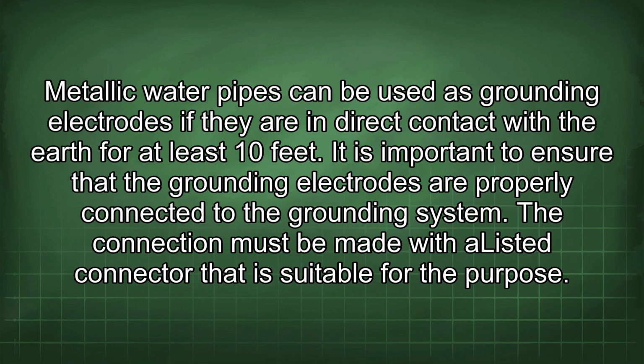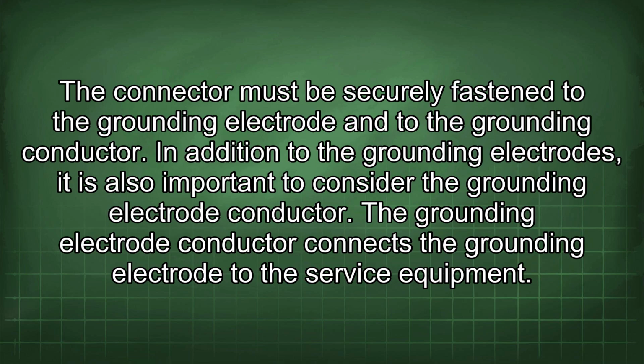Metallic water pipes can be used as grounding electrodes if they are in direct contact with the earth for at least 10 feet. It is important to ensure that the grounding electrodes are properly connected to the grounding system. The connection must be made with a listed connector that is suitable for the purpose. The connector must be securely fastened to the grounding electrode and to the grounding conductor.